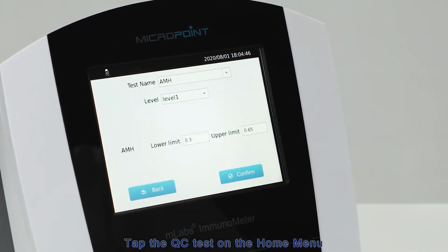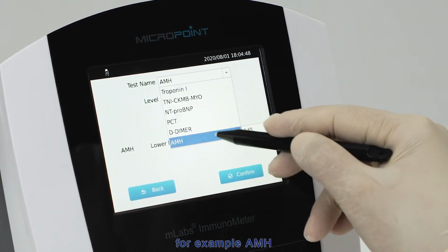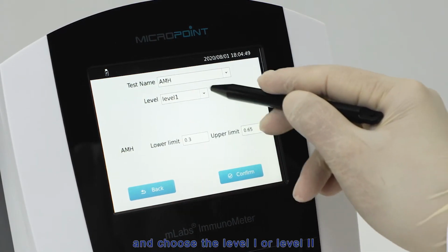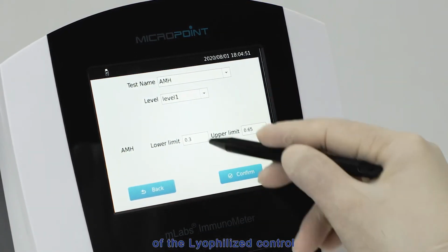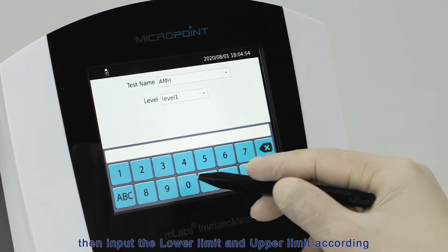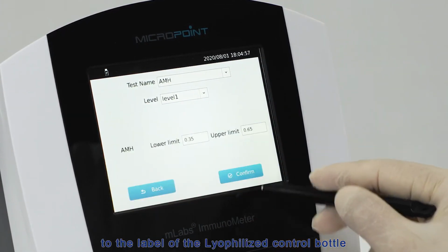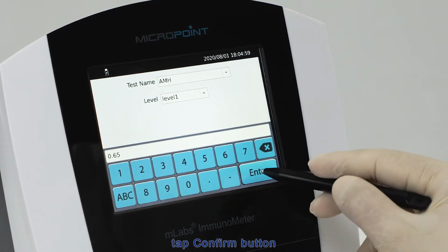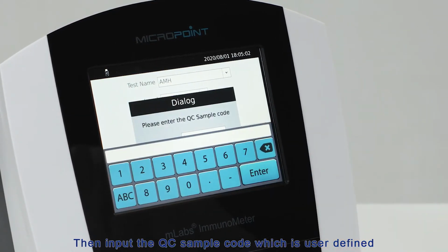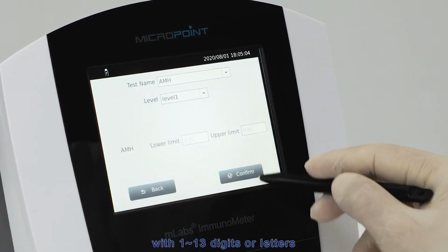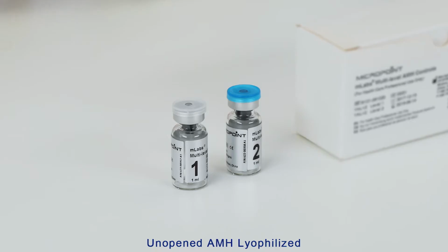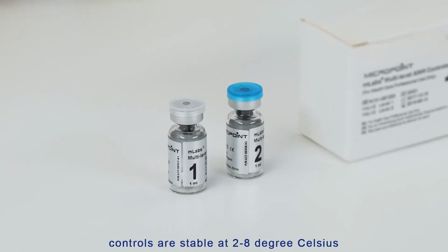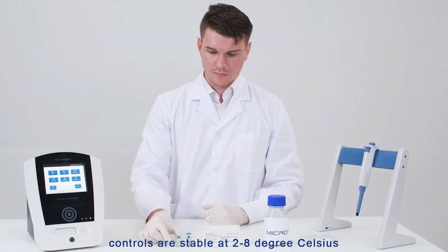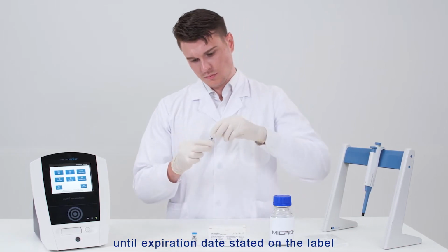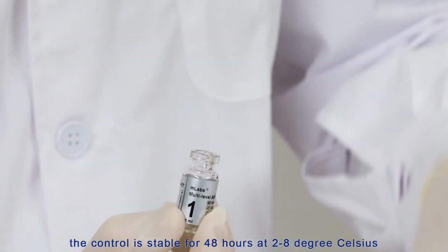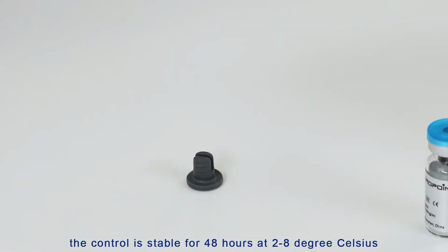Tap the QC test on the Home menu. Choose the test item, for example, AMH, and choose the level 1 or level 2 of the lyophilized control. Then input the lower limit and upper limit according to the label of the lyophilized control bottle. Tap Confirm button. Then input the QC sample code, which is user-defined with 1 to 13 digits or letters. Unopened AMH lyophilized controls are stable at 2 to 8 degrees Celsius until expiration date stated on the label. Once opened, the control is stable for 48 hours at 2 to 8 degrees Celsius.